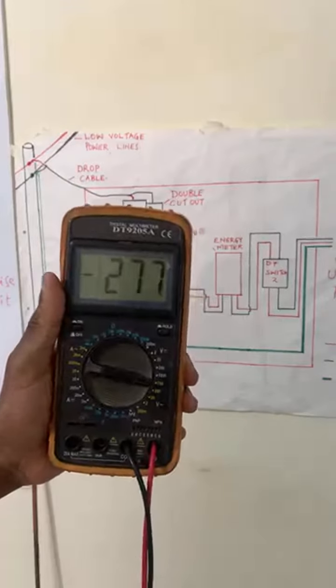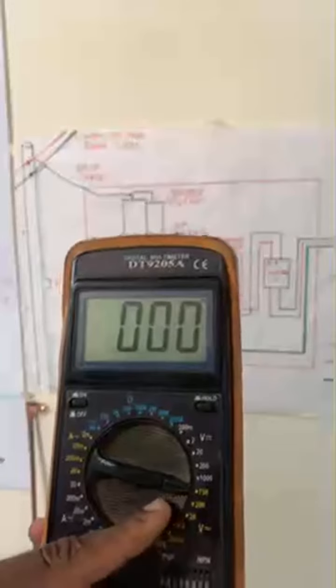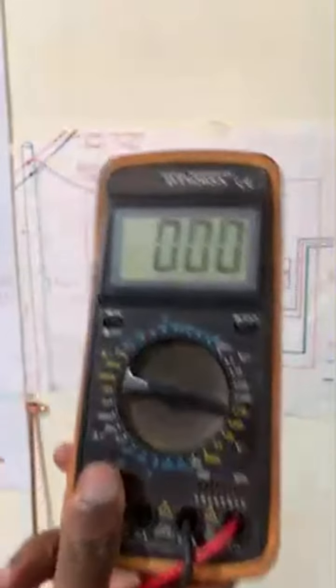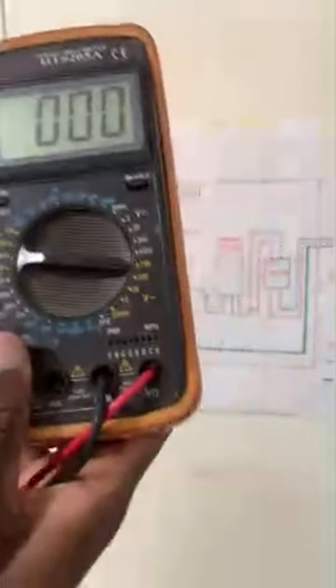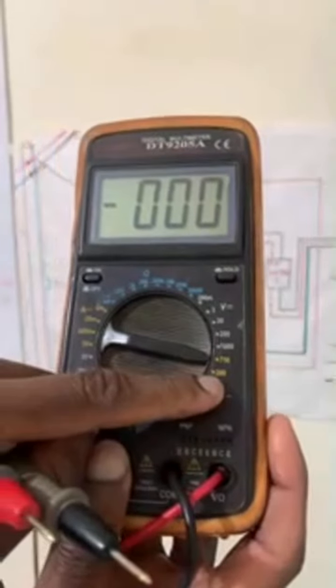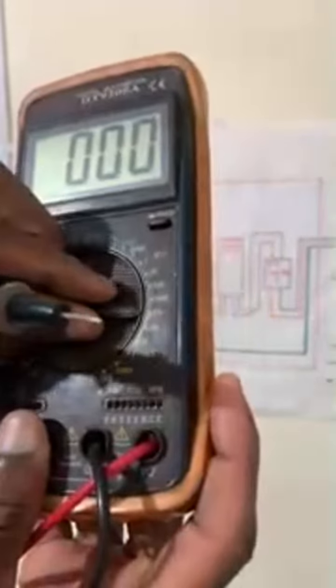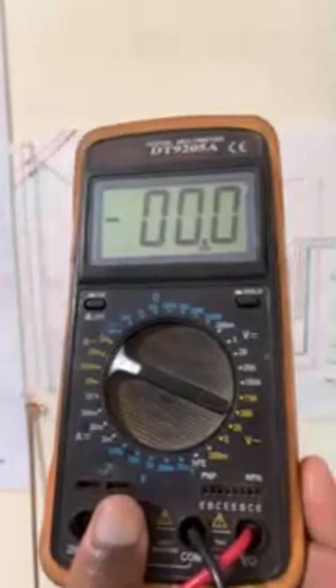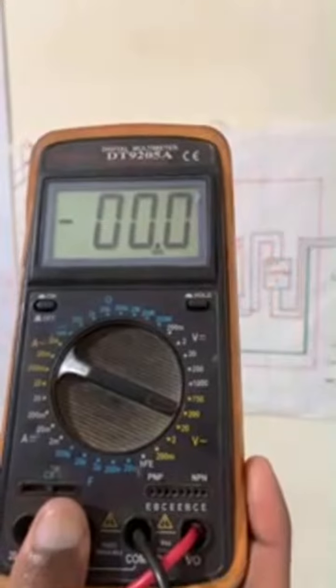So you put this multimeter on, turn it on, and we have several points here where we can take our readings. That is the reading for AC, which is what we are dealing with now. Using your probes, you place one on the phase and one on the neutral to get a reading. If you are expecting 230 volts, for instance, in our country, you place your pointer at 750. In countries like the USA where you expect 100 or 110 volts, you simply turn it to 200 so that you can take the readings you expect.